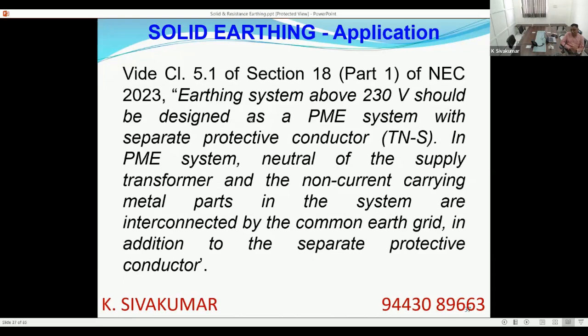That is solidly earthed. So it further explains that in a protective multiple earthing system, the neutral of the supply transformer and the non-current carrying metal parts in the system are interconnected by a common earth grid. That means the transformer neutral is connected solidly to the earth grid. So there is no question, it must be solidly grounded.